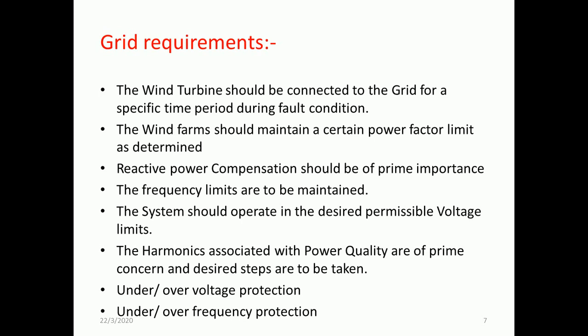What are grid requirements? A wind turbine should stay connected to the grid for a specific time period during a fault condition. It should not be isolated. The wind farm should maintain a certain power factor limit as determined. Reactive power compensation should be of prime importance, and measures like capacitor design and implementation, static VAR compensators, and FACTS devices should be taken on priority. Further, the frequency limits as decided are to be maintained.